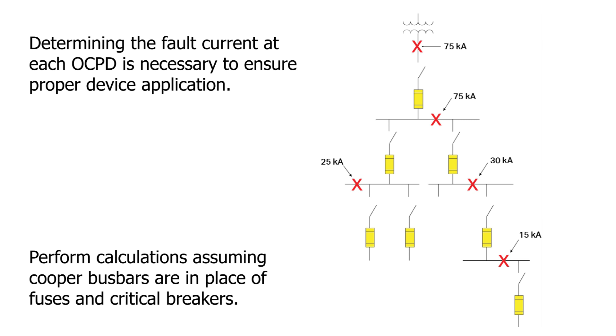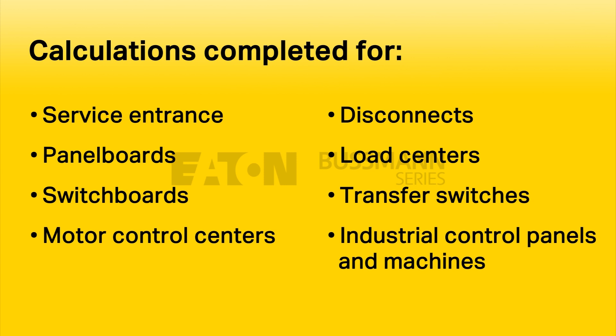Calculations should be made at various points in the electrical system, including service entrance, panel boards, switchboards, motor control centers, disconnects, load centers, transfer switches, industrial control panels, and machines. A quick and simple method to determine the available fault current is to use the Eaton-Bussmann series fault current calculator, available on the App Store or Google Play. It is also available for online use as a free tool to calculate fault currents based on the voltage, transformer size, impedance, and conductor length. Fault current calculations in the palm of your hand.